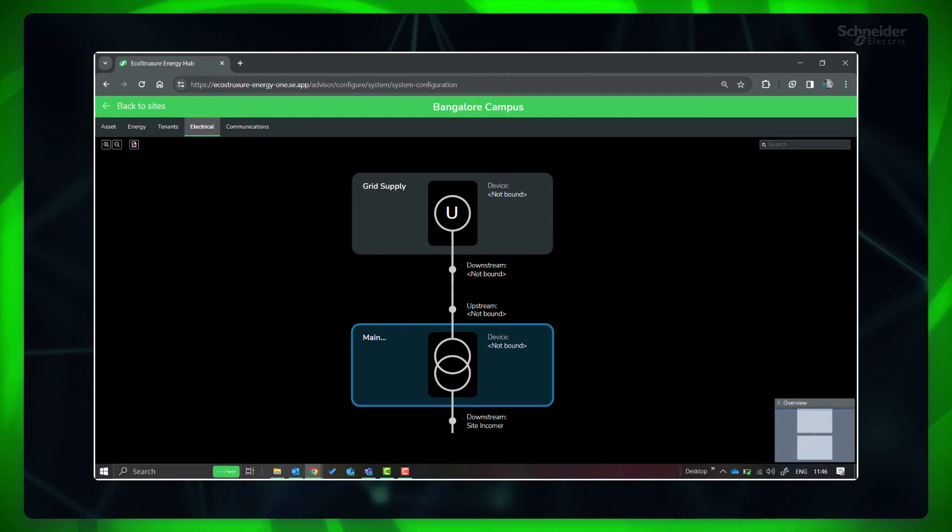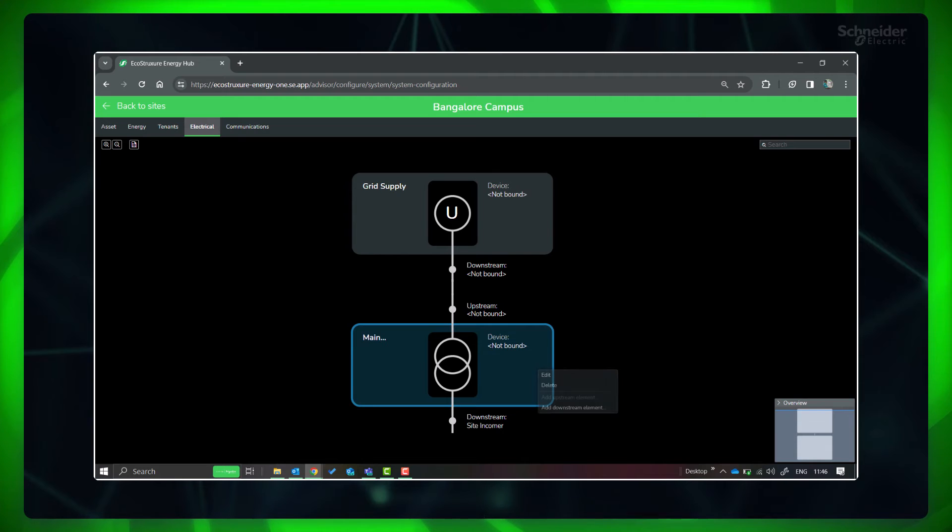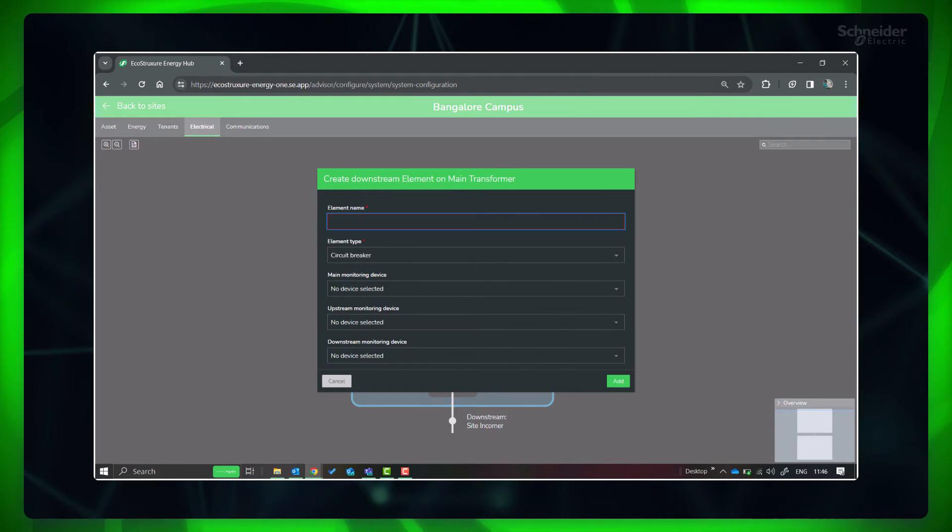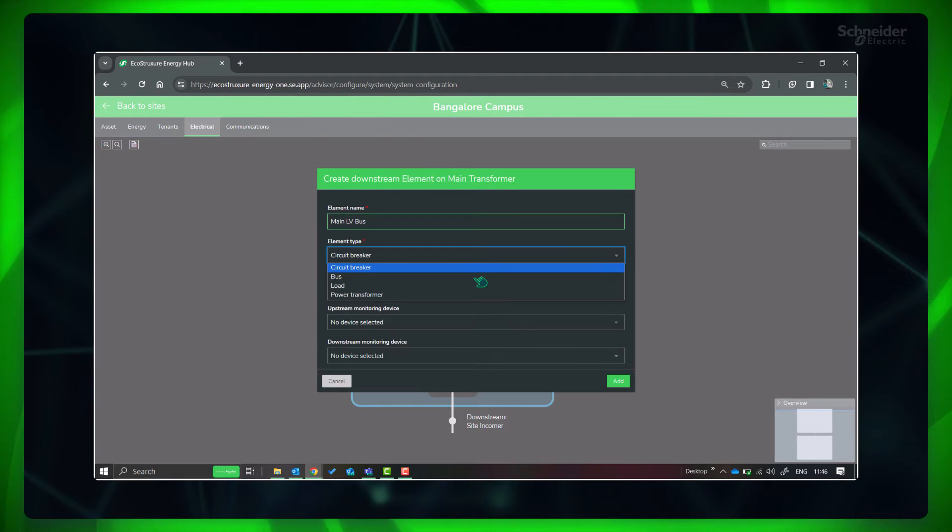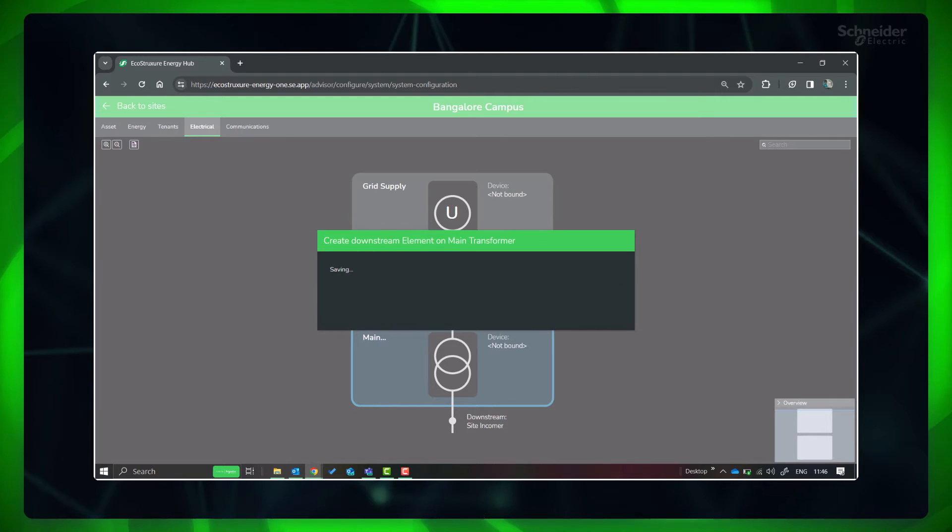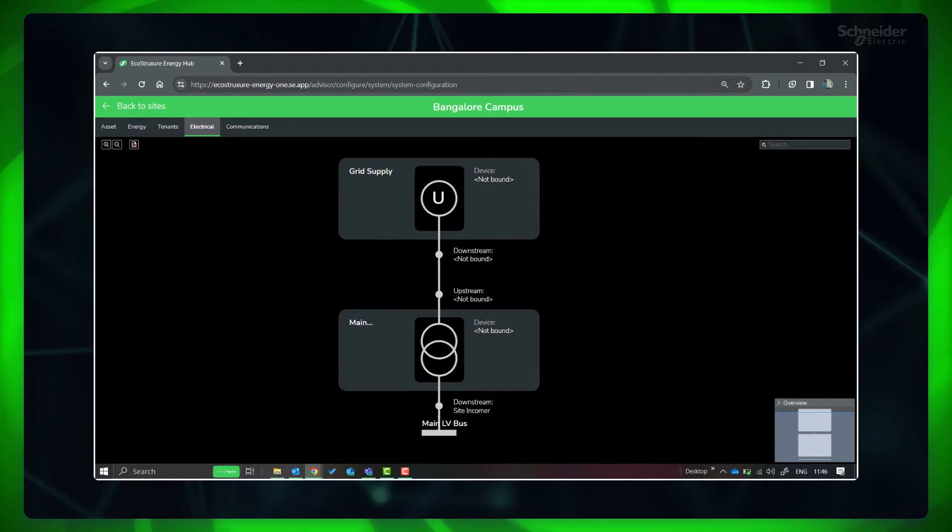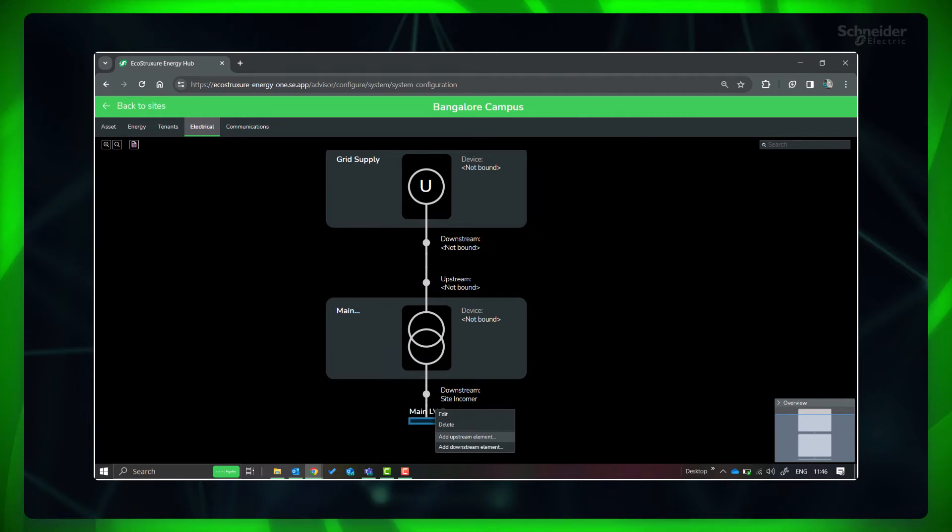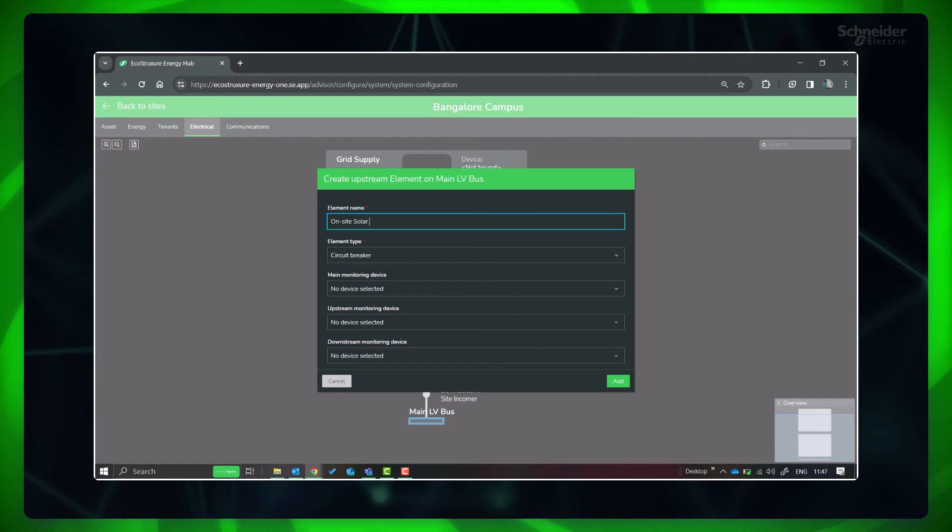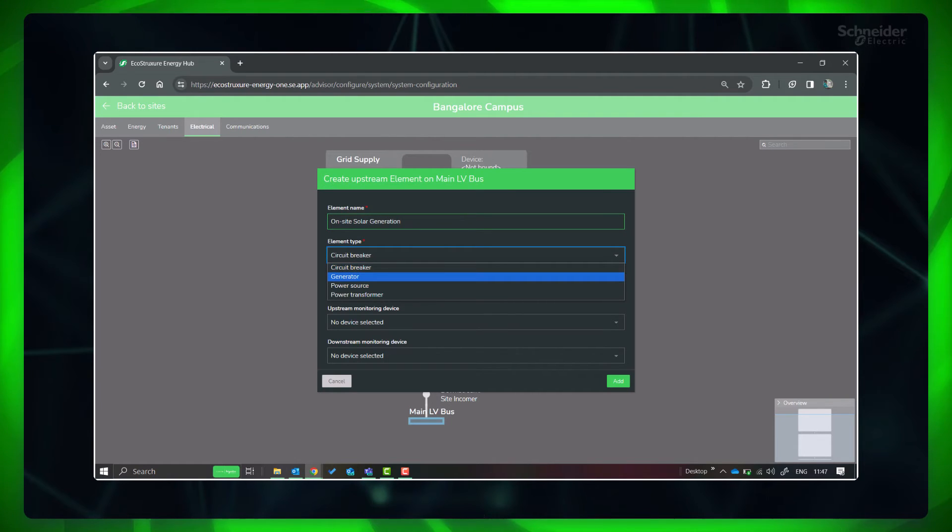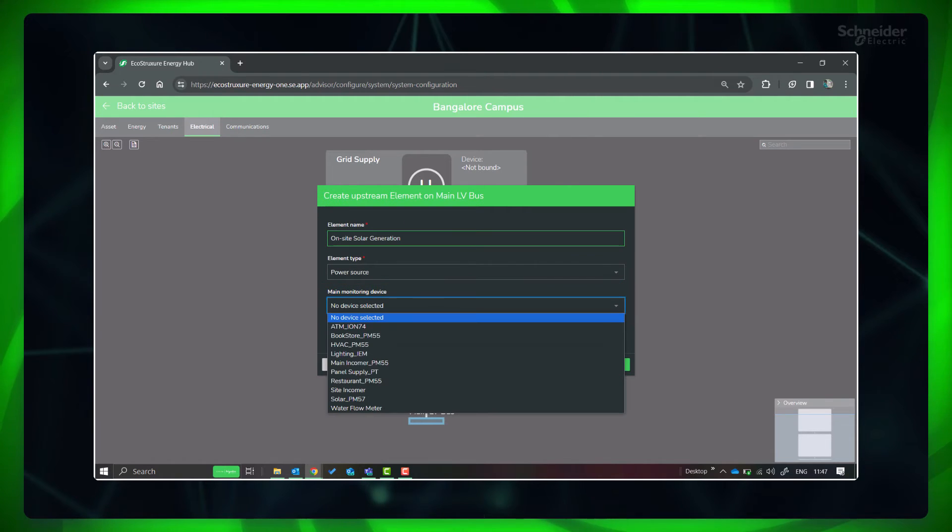Let's add the main LV bus and then add the second source from solar generation. Select the transformer and right click and select Add Downstream Element. Select the element type as bus and provide the name. Select bus and right click and select Add Upstream Element. Select the element type as power source and provide the name. Select the respective monitoring device if available.